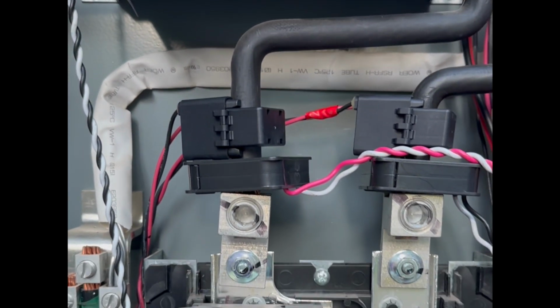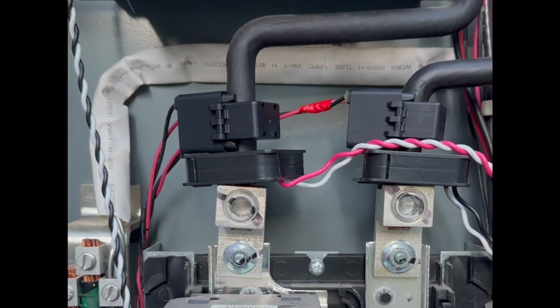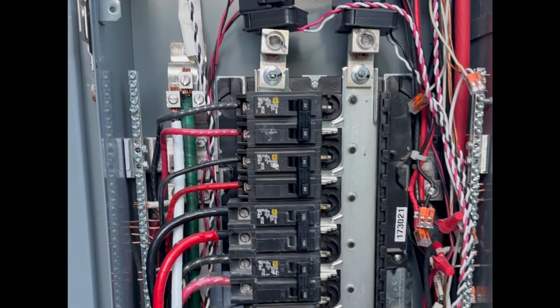But wait a second, could that have been the problem with CT1 and CT2 all along? Not upside down, but on the wrong phase? Let's go take a look. Every panel I've been in has the black phase on the left bus bar and the red phase on the right. In fact, you can see from the alternating black and red wires on the breakers on the left side of these bus bars that whoever wired these breakers in assumed the same thing. The top left wire is black, which connects to the first spade from the bus attached to the left lug.